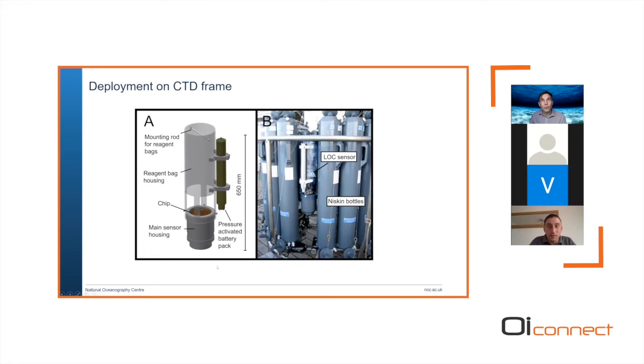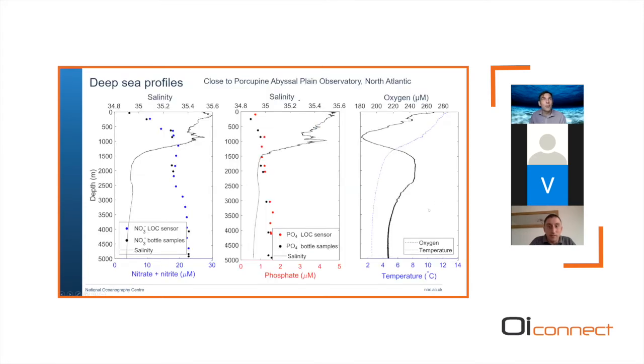We've made it easy for oceanographers to fit these to a CTD frame. Here's a clip with an integral battery pack, so they can be clipped to a standard ship-based CTD system. And we can get some really deep sea profiles. One of the advantages of our technology is that the electronics and all the systems are deep sea rated. Not actually that much more expensive to achieve that. In fact, now we've done it, there is really no extra expense, and it means we can make measurements down to 6,000 meters. Here's some data where we've got measurements, nitrate and phosphate, down to 4,800 meters.